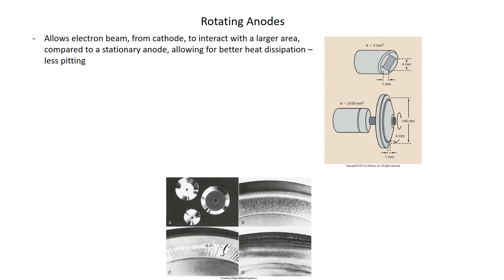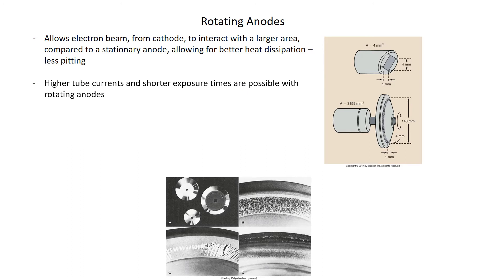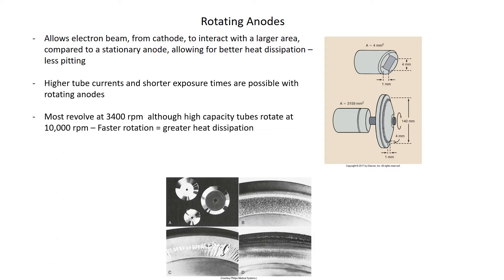Rotating anodes allow the electron beam from the cathode to interact with a larger area compared to a stationary anode, allowing for better heat dissipation and less pitting. You can see examples of anodes whose faces have been pitted. Rotating anodes also allow for higher tube currents and shorter exposure times. Most revolve at 3,400 RPM, although high-capacity tubes rotate at about 10,000 RPM — faster rotation means greater heat dissipation.